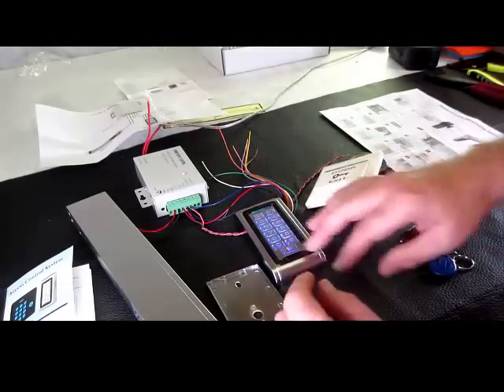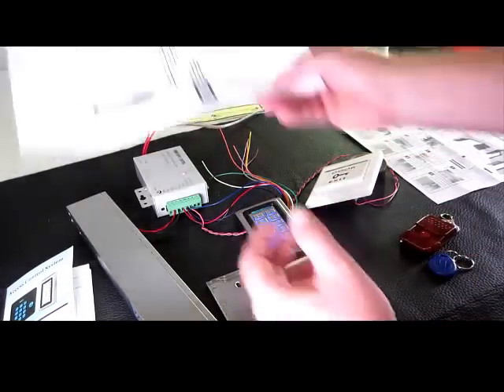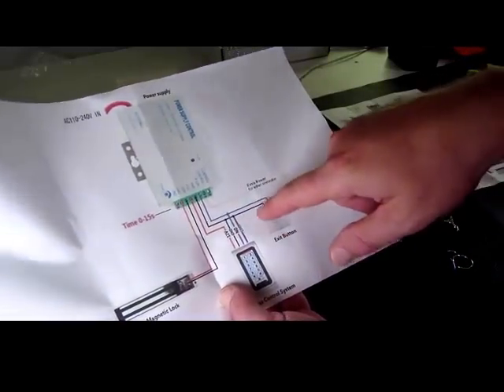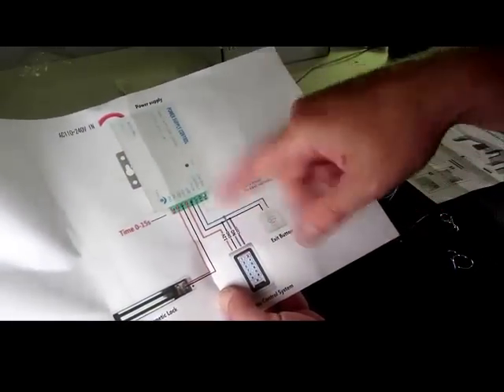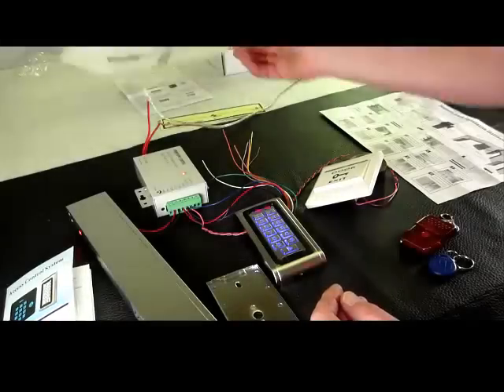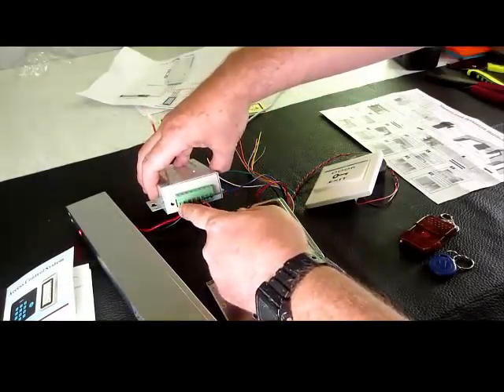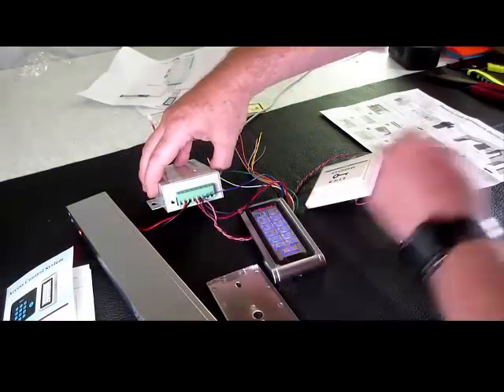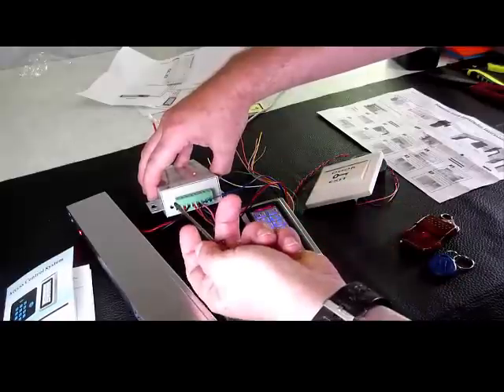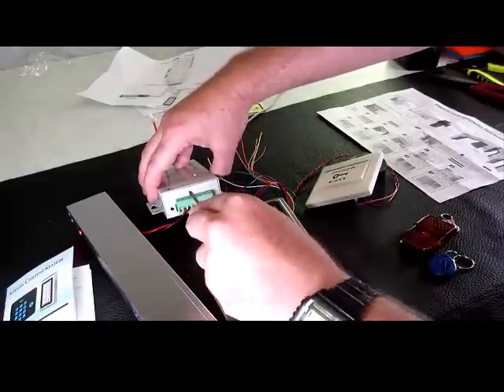The wiring is pretty straightforward if you follow the manual as it dictates. Connect these together, your common and your ground to one side of the push button switch to push button output, very straightforward. Two wires to the magnetic lock, it works like a charm. Over here there's a potentiometer so that way you can take a little screwdriver like this and you could turn it from zero seconds to the far left all the way up to 15 seconds.